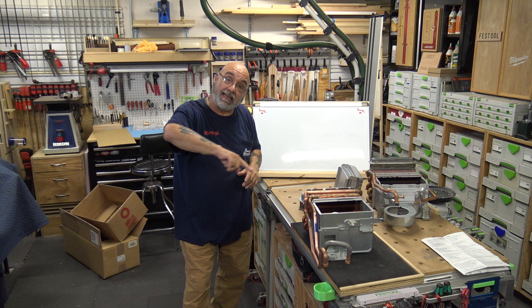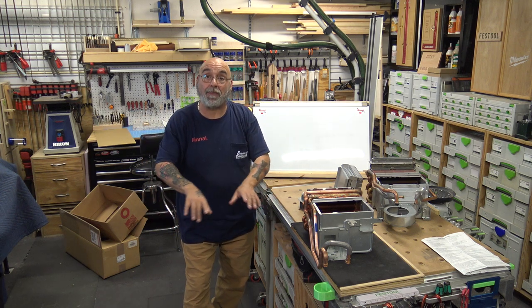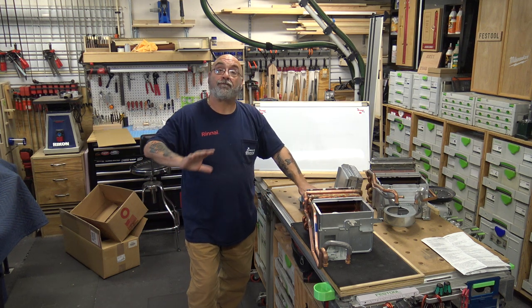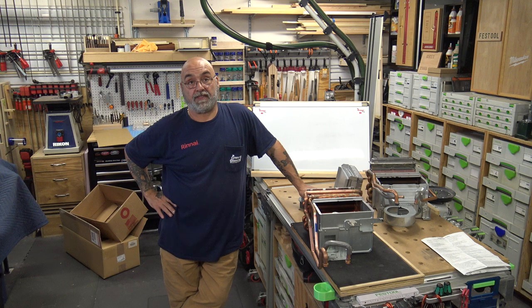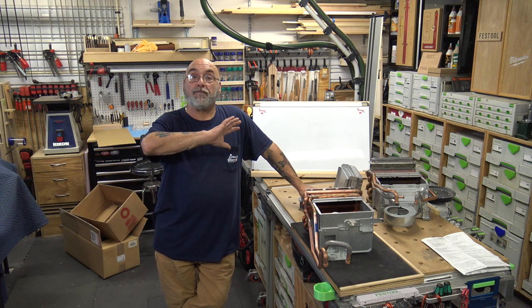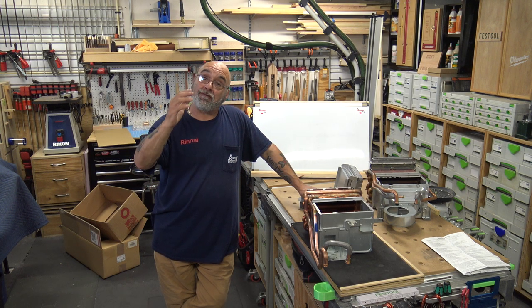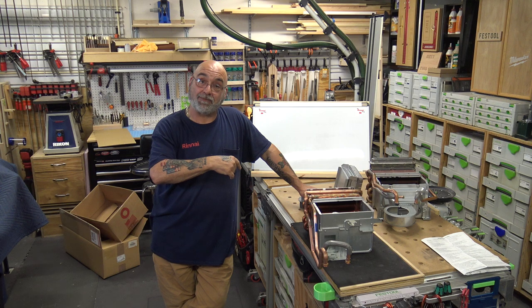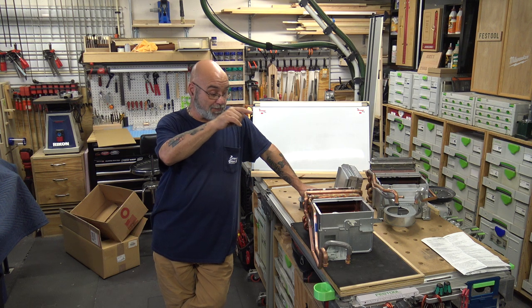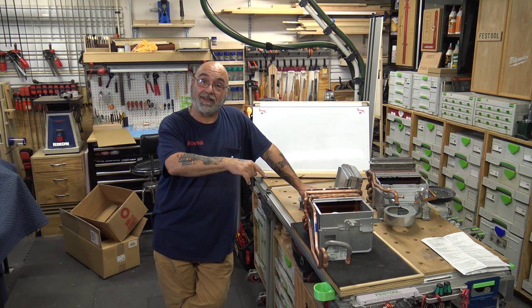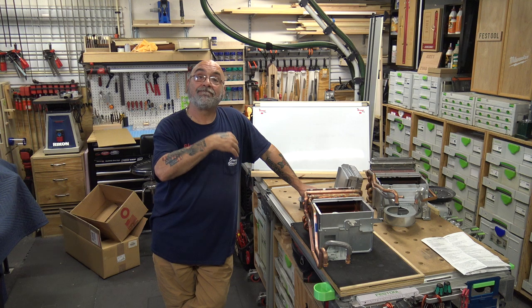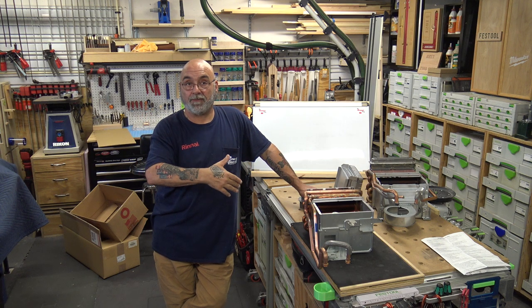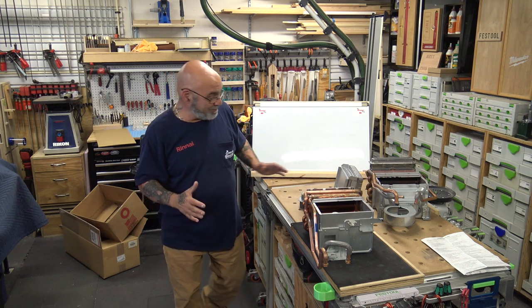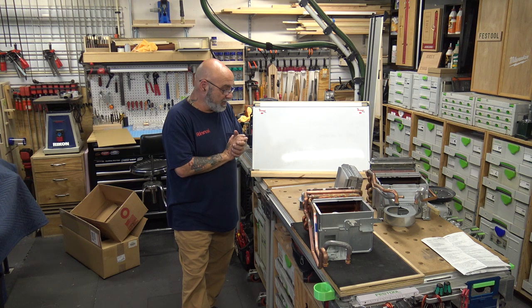Also, you want to look inside of the chassis on the bottom. Look, you're going to find all kinds of stuff in there. Take your vacuum, vacuum that out, because eventually that's going to make its way into the fan, and it's going to make its way into the burner, into the heat exchanger, and then you're back to a code 10. Okay, so that is your...